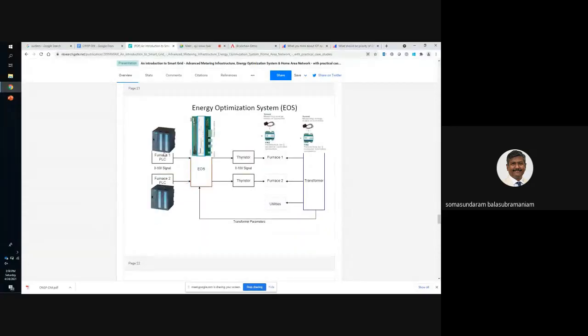You can see from the PLC there is a signal coming to the thyristor, in the form of 0 to 10 volt. In between, we inserted an embedded system, and this acts as a hardware between the thyristor and the PLC. This hardware communicates to the upper-level systems, which keep track of the load of each and every transformer.